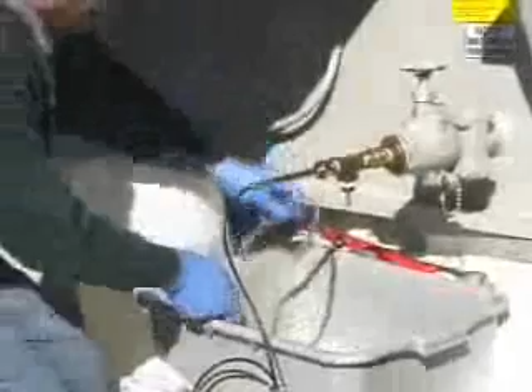The last part of the sampling process is to clean up our area before we leave. Now what we're doing here is what we would do on a sample as well. Although we have the moisture probe installed, we would remove the moisture probe by checking to make sure that the drain valve is closed and then undoing the moisture probe from the drain valve. You will see that there's some oil in the manifold of the moisture sensor as well. And we have to make sure that we capture that oil so it doesn't spill on the ground.